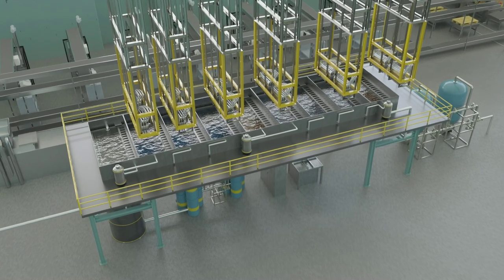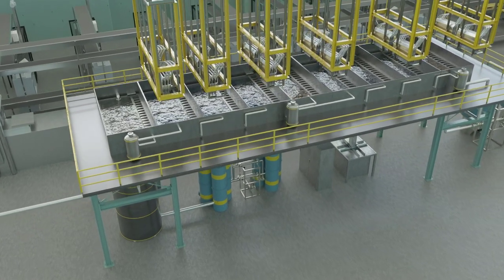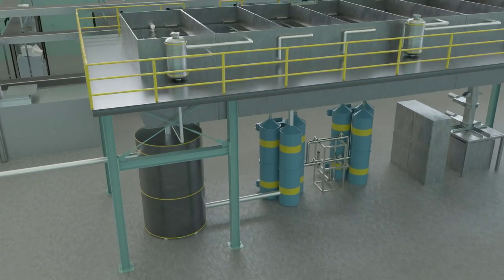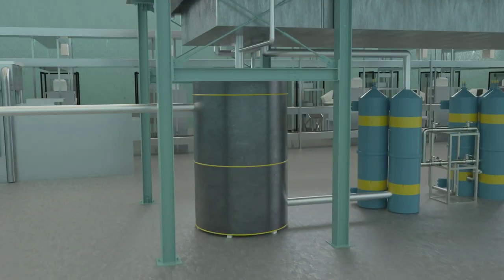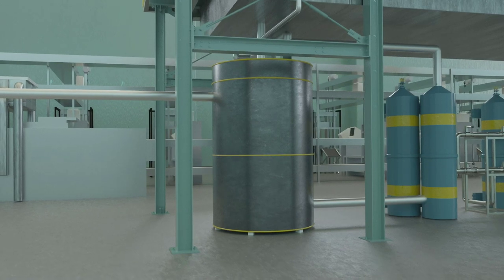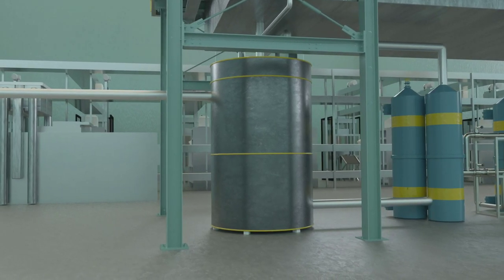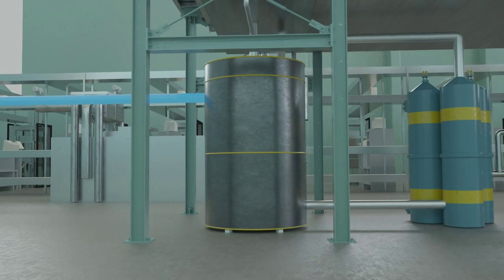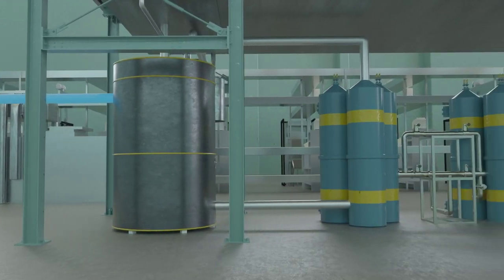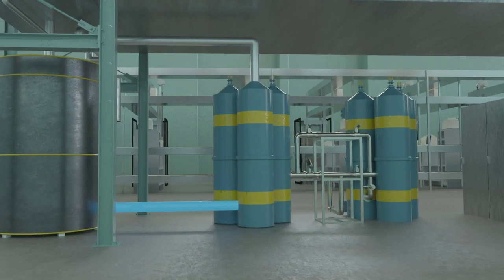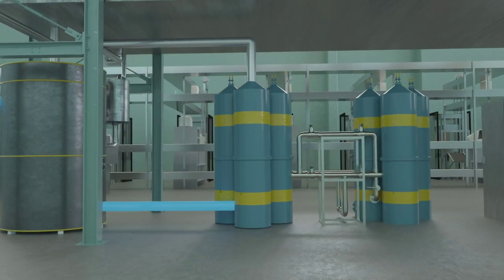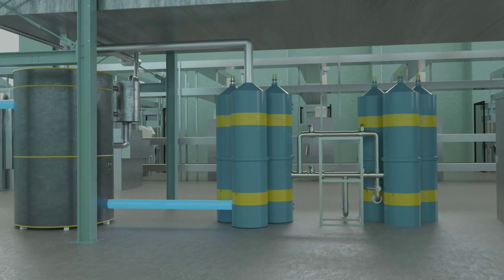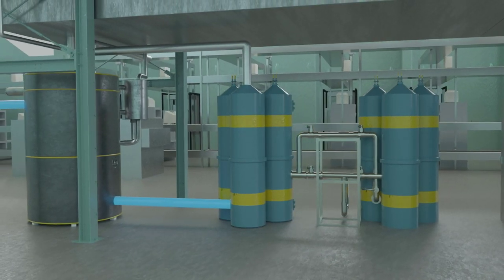In order to save water, chemicals and energy, the rinsing water is used several times in the new system. The fresh water, which is used for all rinsing processes, first flows into a large collecting tank under the site. An ion exchanger takes it and produces fully demineralized water.